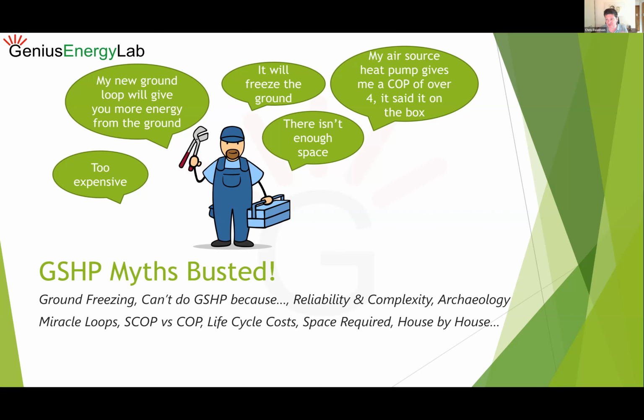Touched on archaeology, it's no problem really. Miracle loops is another one - I'll get probably once or twice a year a company coming to the marketplace saying our ground loop with this coil and that pipe will give you 6 times what anything else in the marketplace will. What I can absolutely tell you is that if the ground won't give it to you, you cannot take it out. That might be true if you've got a very highly conductive ground condition, but in the majority of cases, there's no way one loop is going to have a massively significant difference over the other loop architecture.